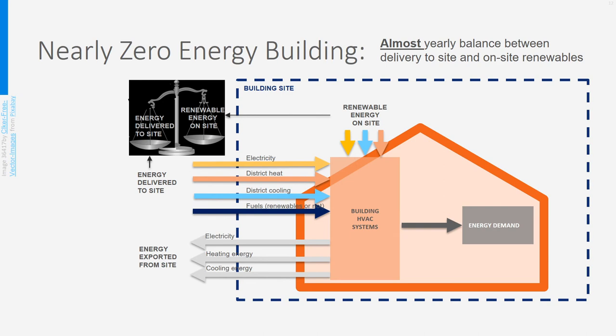Let's move on to nearly zero energy buildings. Be aware that the abbreviation is also NZEB — the same as for net zero energy buildings, which is very confusing. In these buildings, a small deviation from the yearly balance is accepted, meaning that producing slightly less renewable energy on-site than needed to balance the energy delivered is allowed. How large this deviation is depends on national and local agreements. For instance, European guidelines indicate a maximum imbalance of 45 kWh per square meter. Just as with net zero energy buildings, many different definitions can be found.